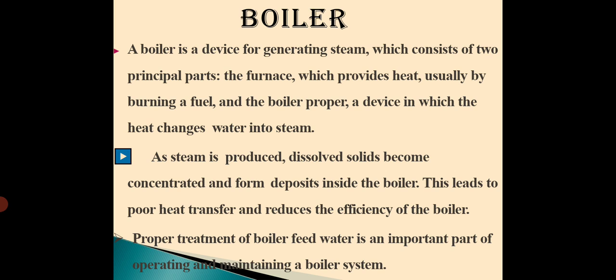Before entering into the topic, we should know what is a boiler. A boiler is a device for generating steam and consists of two parts: the furnace and the boiler proper. The furnace provides heat usually by burning a fuel, and the boiler proper is a device in which heat changes water into steam. As steam is produced, dissolved solids become concentrated and form deposits inside the boiler. This leads to poor heat transfer and reduces the efficiency of the boiler. Hence, proper treatment of boiler feed water is an important part in operating and maintaining a boiler system.